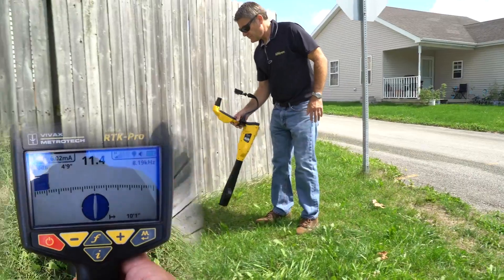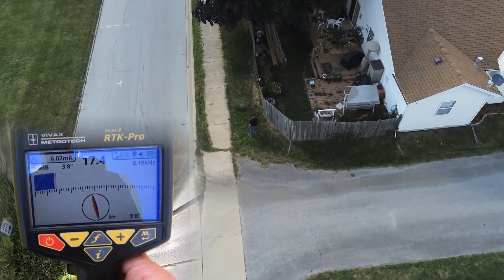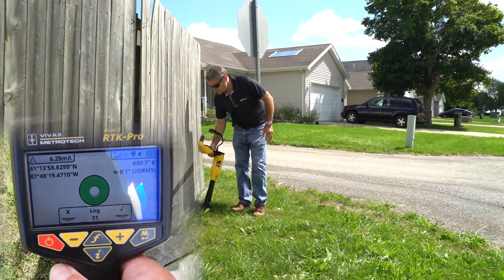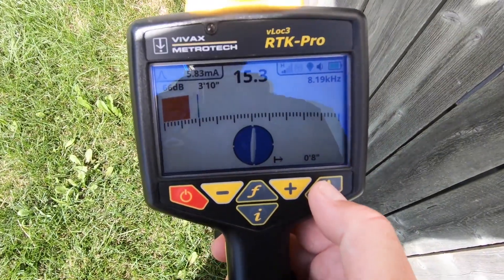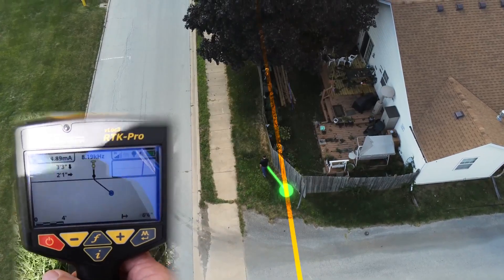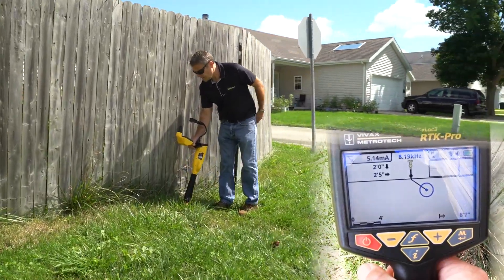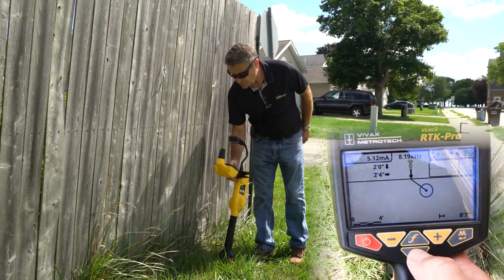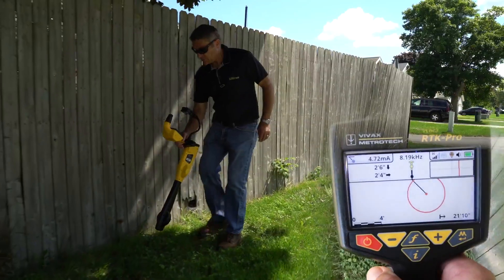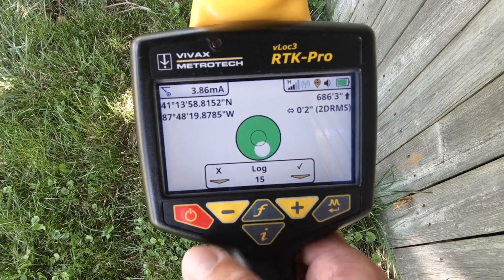Here we have a fence where it goes over our utility. We'll capture one point here, and then we'll have to switch to vector mode in order to capture the data. We still have the current, the depth of cover, and it's telling us it is actually inside the owner's property at about two foot four inches, so I will take that data point. Continuing along — a lot of distortion now, some interference that obviously we can't control. I'll take that data point.